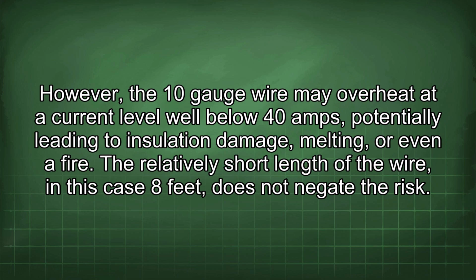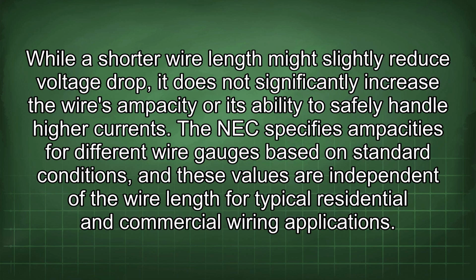The relatively short length of the wire, in this case 8 feet, does not negate the risk. While a shorter wire length might slightly reduce voltage drop, it does not significantly increase the wire's ampacity or its ability to safely handle higher currents. The NEC specifies ampacities for different wire gauges based on standard conditions, and these values are independent of the wire length for typical residential and commercial wiring applications.